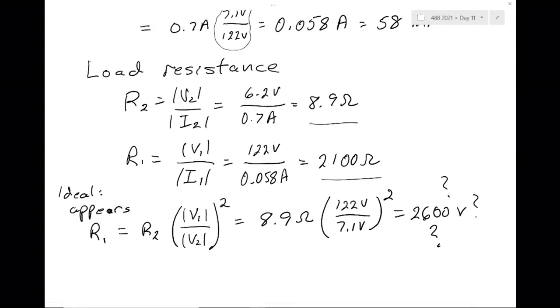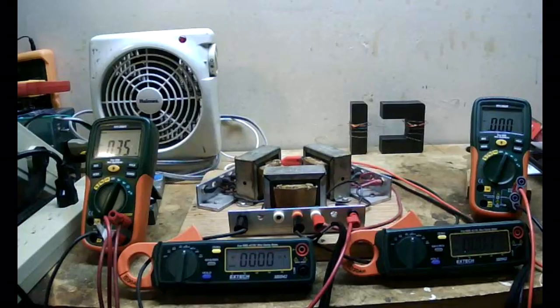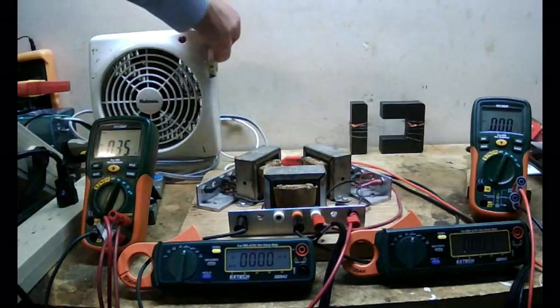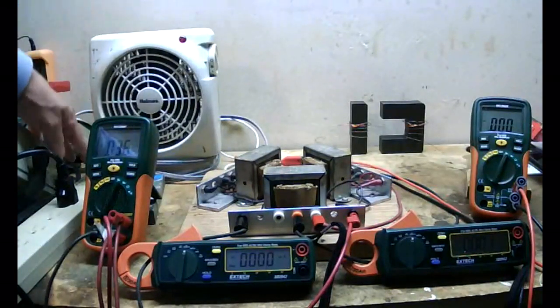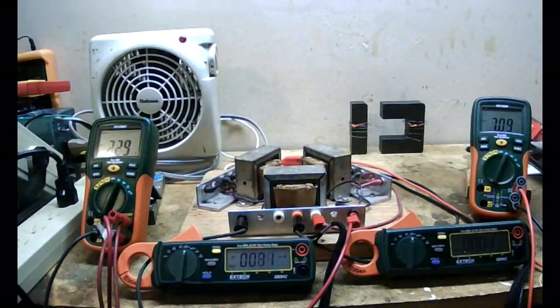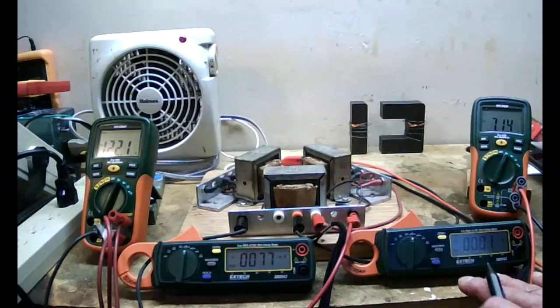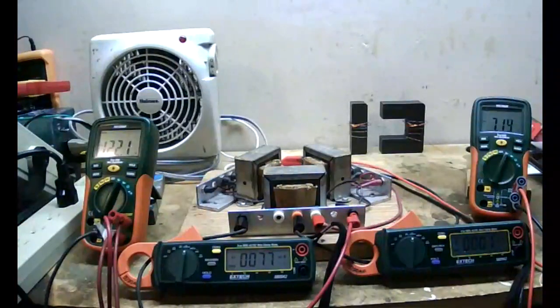You may have noticed that when I was doing the measurements, which I will show you again, the primary current also was not what we calculated. We calculated a primary current under load of 58 milliamps. Let's see what it actually is. Looking at the actual transformer as it is set up, I have the space heater turned off, so there's no load on the circuit. I energize the circuit, and I have about 7.1 volts on the secondary, about 122 volts on the primary, so the same as they were before. Current on the secondary is reading 1 milliamp. We know that's zero because it's open circuit.